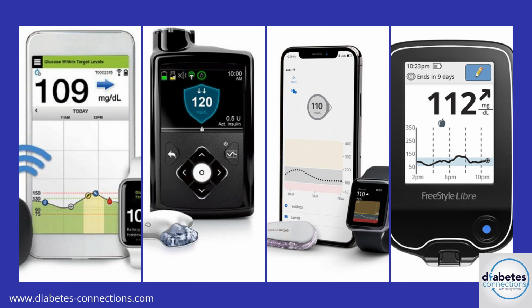And as far as calibration goes, another thing that's important to make sure the system operates properly is that if you do finger stick and see a discrepancy of more than 20%, it is a good idea to calibrate. Enter that reading as a calibration. Otherwise, the CGM is going to continue to underperform. If it's drifted out of range and is running higher or lower than the actual glucose, if you don't calibrate it, it's never going to get back on track. So it is necessary to calibrate when it's not running accurately.